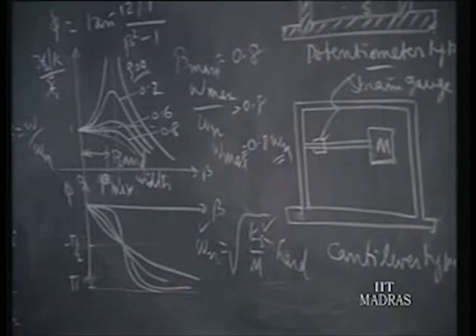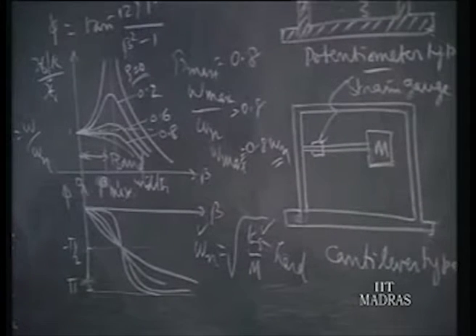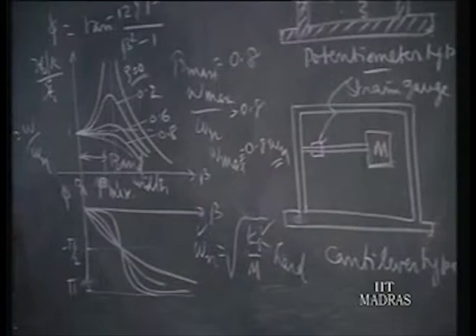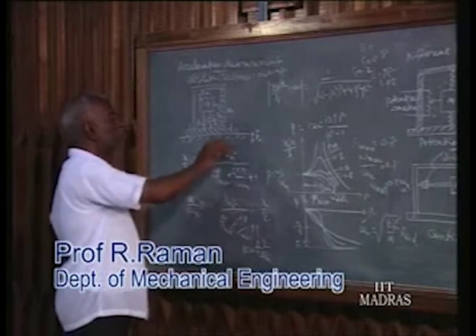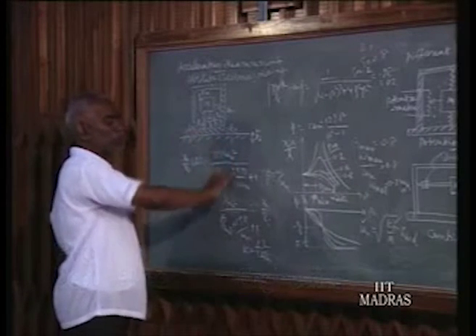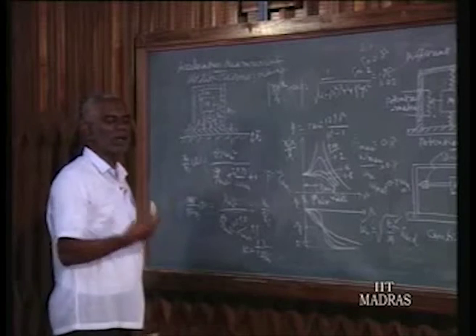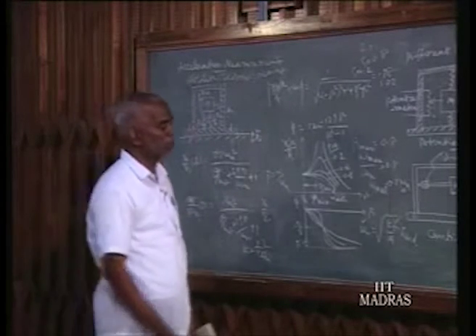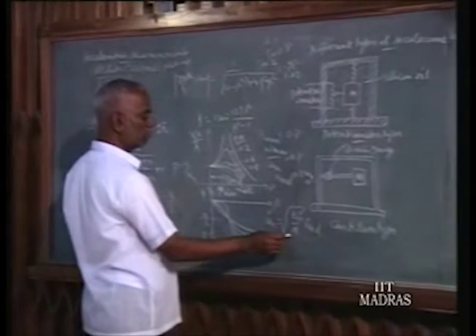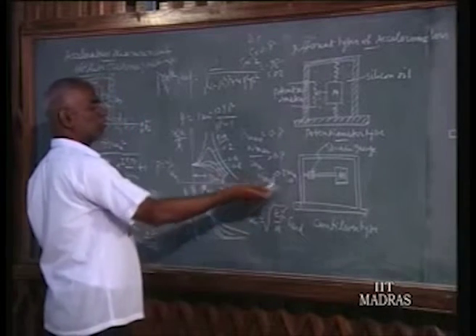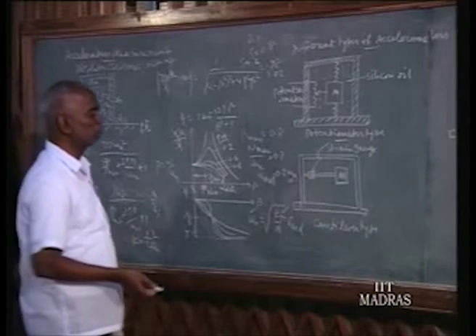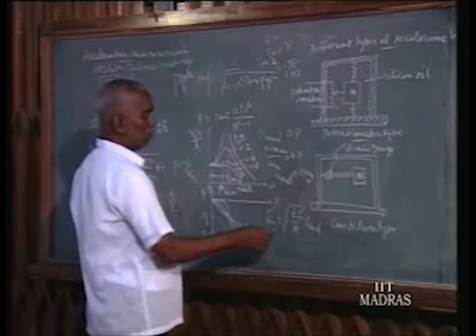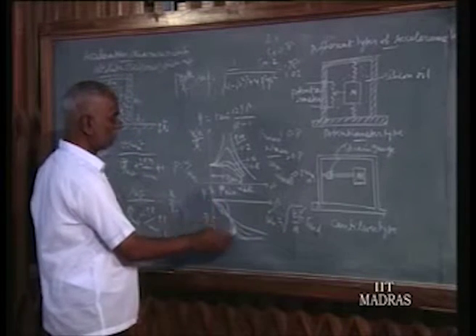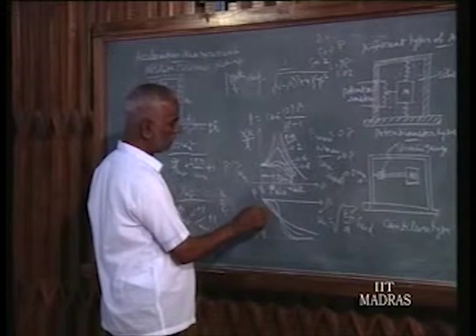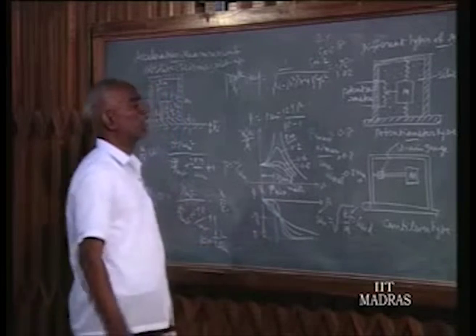So for measuring velocity and displacement using a seismic pickup, we should have a soft spring. But for acceleration measurement, the instrument is the same, but the spring we select should be a hard spring. That is the main difference in the design of the seismic pickup for displacement and velocity versus acceleration. Also, to have a large omega n, the mass should be small. That is possible, and a smaller mass will not give rise to any loading effect. So generally a harder spring is selected. That is the bandwidth, and as for the phase difference, within the bandwidth for psi equal to 0.6 or 0.8 it is more or less linear, so this is what we can accept.